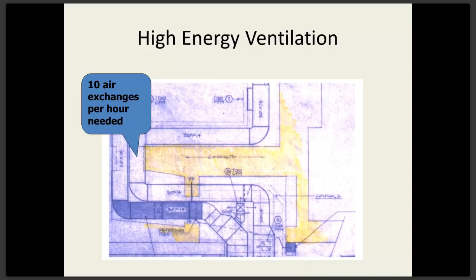I mentioned ozone, and in a room design, the HVAC people will always design for at least 10 exchanges per hour, 10 full air exchanges per hour. That gets rid of the ozone produced from the bombardment of high energy radiation with the oxygen in the room air. It also gets rid of any airborne radioactive material produced by the neutron contamination that we spoke about yesterday. Neutrons can make things radioactive. Sometimes gases are made radioactive from the neutrons. There's outgassing of radioactive gases from the different parts within the machine. And 10 exchanges per hour keeps the room safe from a respiratory standpoint.